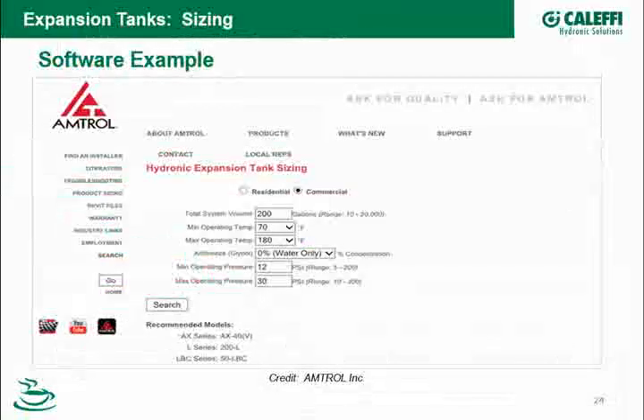Jody, everybody, yes. Just a quick clarification. When you're talking pressure, you're talking gauge pressure, not absolute pressure, correct? That is correct. That's a very good point. These are all gauge pressures. Okay. And then as it relates to determining the minimum operating temperature, you're showing an example on this Amtrol spreadsheet of 70. Depending on your installation, that could be 50, it could be 40, something less than that. You could be in a chilled water application and cooler yet. Is that correct? Yes.